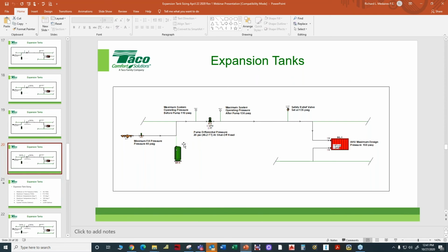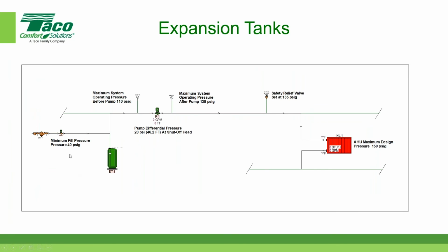The reason that you connect the expansion tank to the suction side of the pump is because that's the point of no pressure change. So in our case, we start off with a minimum pressure of 40 pounds. That's our fill pressure, assuming for a moment that we have not started heating the system, which means that the water temperature is still fixed at the fill temperature, in our case, 50 degrees Fahrenheit. When I start the pump, the pressure at the suction side of the pump will remain constant because it'll be the fill pressure in this case.